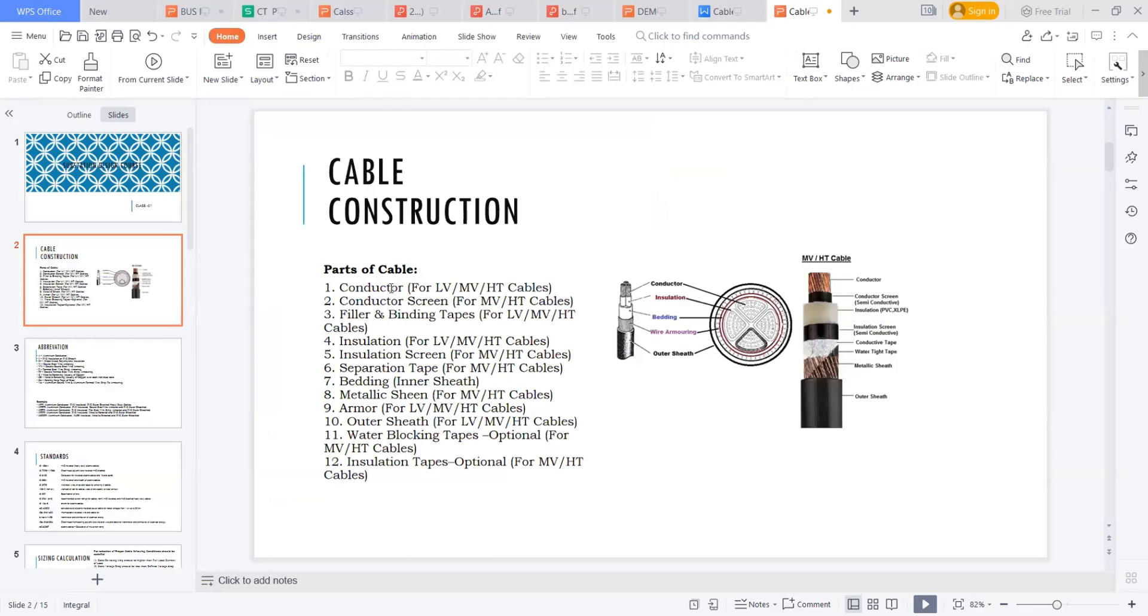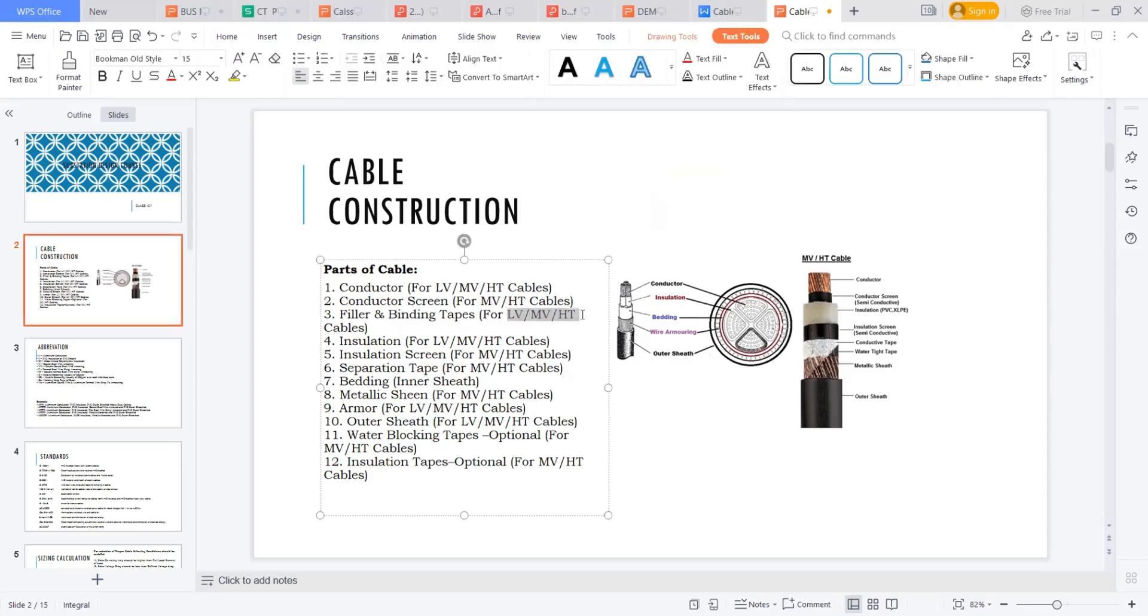The conductor is a general core material applicable for all voltage classes. The conductor screen, which is on top of the conductor, is generally extruded semiconductor compounding material to make uniformity on the voltage stresses across the cable. The filler and binding tapes are also applicable for all voltage classes to make a good circular shape of the cable if I'm having some segmented or three core cable.